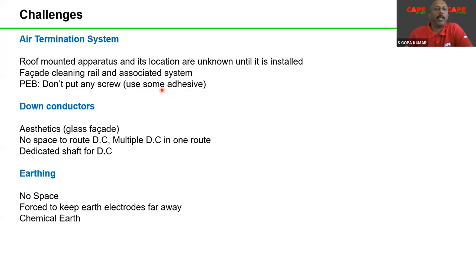So that means the effectiveness of lightning protection is gone. The second challenge which we always face is the down conductor. In large multi-storied buildings, if we say that the down conductor has to be outside the building, then the first answer is no, no, no. That part of the building, there is glass facade. This part of the building, glass facade. So it will affect the aesthetics.